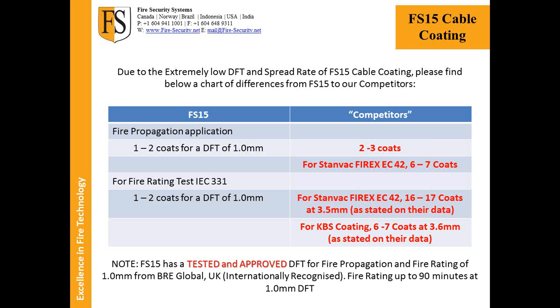It's amazing. Same with KBS coating. KBS coating has a 3.6 millimeter dry film thickness for its IEC rating, achievable up to 52 minutes, but it takes 6 to 7 coats to achieve that thickness, because suddenly your cable coating, which should be a low build coating, single 1 or 2 coats, has become a high build coating where you're anywhere between 6 to 17 layers of coating to achieve that designated thickness. That can't be good for the end user, especially when you can spray FS15, 1 to 2 coats, and you walk away.